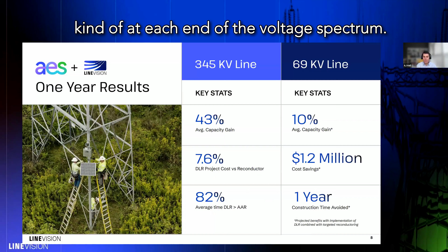We've had LineVision sensors deployed for over a year on our lines now, with some very positive results. We're showcasing two lines at each end of the voltage spectrum. On the left, a 345 kV line in Indiana showed an average capacity gain above static ratings of 43%—a lot of bandwidth or headroom to be gained by deploying DLR. Compared to the cost of reconductoring that line to achieve that same 43% gain, DLR cost less than 8% of a standard reconductor.